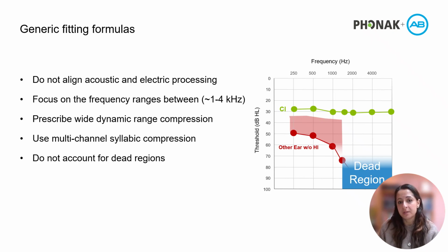Let's take a look at what happens during a bimodal hearing aid fitting that is not part of a true bimodal system. These hearing aids are fitted with generic hearing aid formulas, for example NAL or DSL. These formulas do not align acoustic and electric processing. That's required for optimal bimodal hearing. Generic fitting formulas focus their amplification in the high frequency region of 1 to 4 kHz. And while high frequencies are typically most important for speech understanding, for severe hearing loss, they're also the frequencies where dead regions in the cochlea most likely occur.